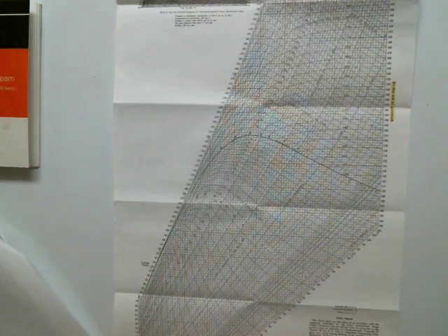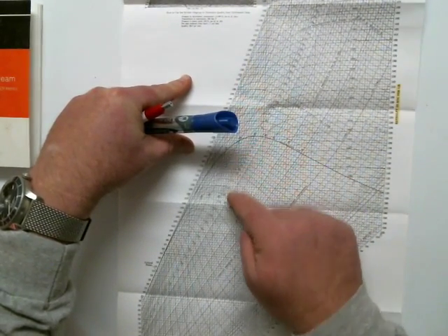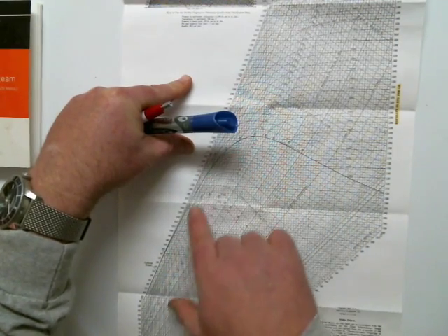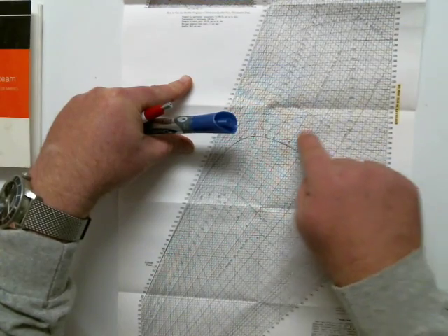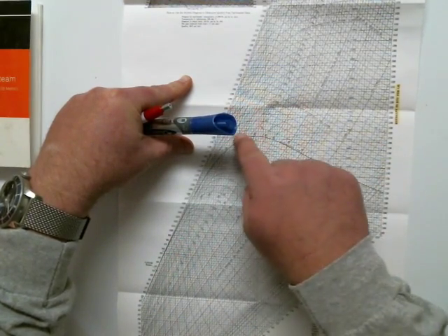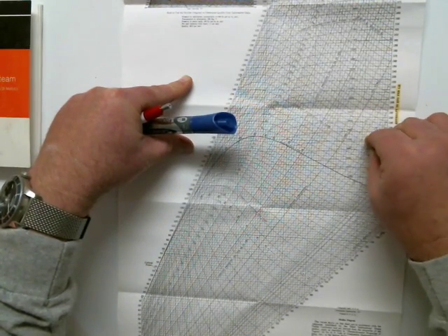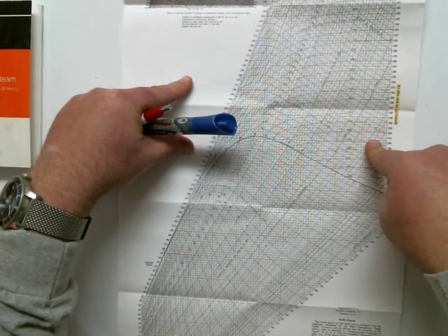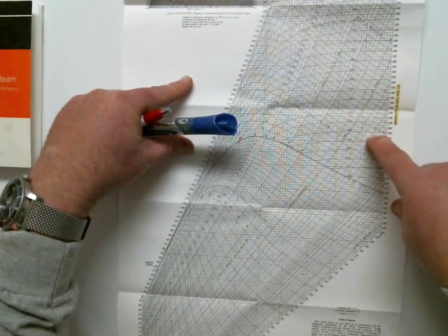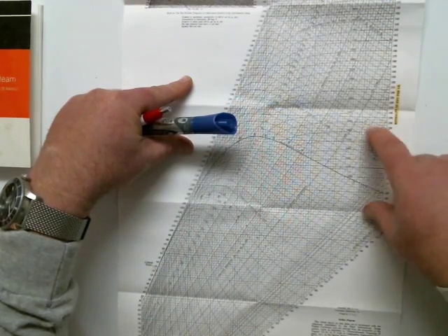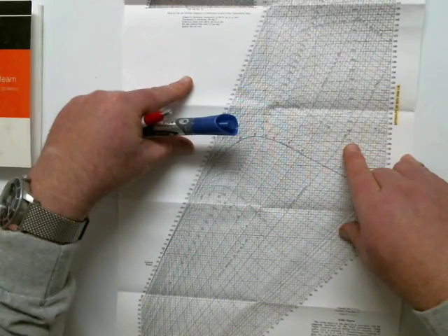It's not that hard. We'll have a ruler going this way, top to bottom, dropping pressure, and you can see that I'm lowering the enthalpy. So this will be a turbine dropping pressure this way. If it's a constant enthalpy process, we're going to find out that I dropped pressure through an open safety relief valve, that's a constant enthalpy process, and the outlet of it, of the SRV down in the torus or in your suppression pool, is going to be superheated steam. And we can figure out what the temperature of that superheated steam is supposed to be. And you'll see that it's going to be much less than expected sometimes.